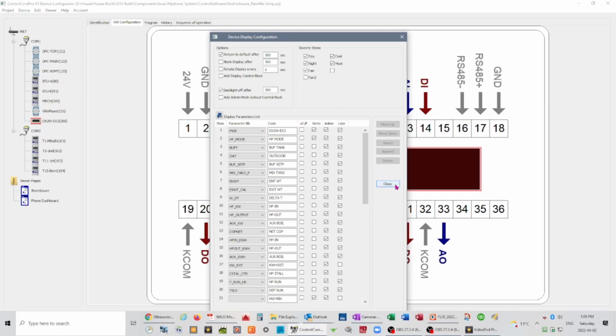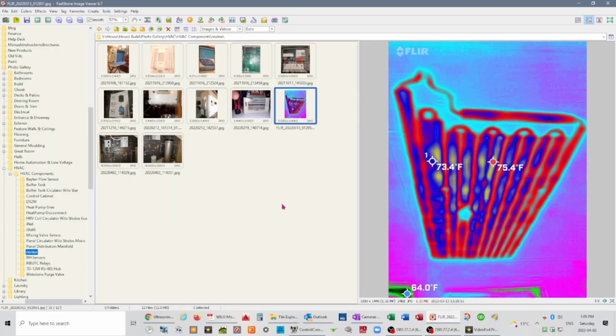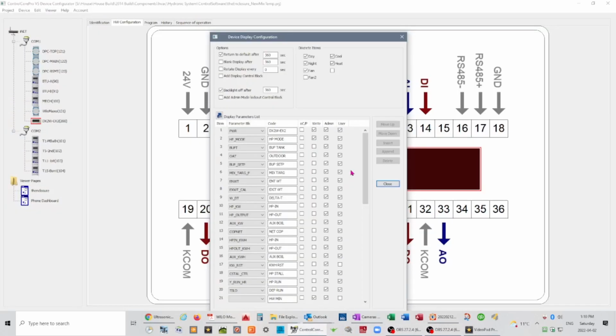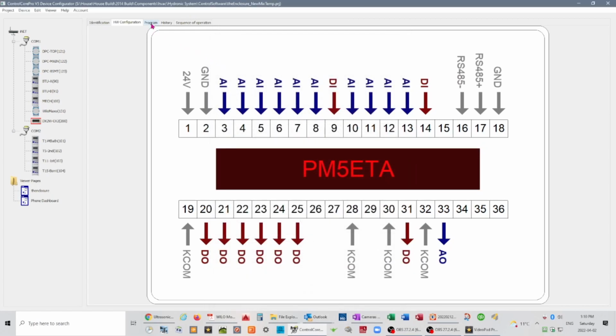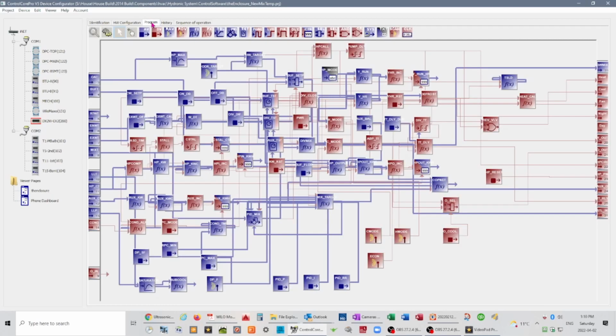That will then show up on the LCD display on the actual device. So if we go back down to here, whatever you put in the parameters list is actually going to show up on this LCD here. These buttons allow you to scroll through the parameters, and the middle buttons allow you to set the settable parameters. Once you've identified the input-output types and determined your parameter list that is going to show up on your LCD screen, now you get into the actual programming of the device.